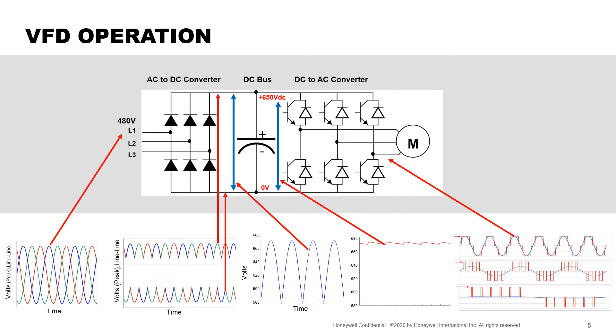So to summarize that, a VFD takes AC power and converts it to DC in the rectifier section. The DC bus smooths out the ripples and the IGBTs pulse it to the motor in a simulated AC current. The VFD can be controlled by a sensor or a controller to drive at a certain frequency. This saves energy and conditions the space better.